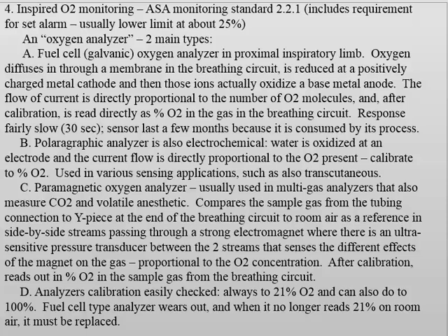There's the so-called polarographic, which is electrochemical, very rare anymore, unlikely to be the subject of a question. The paramagnetic oxygen analyzers are what's in the gas analyzers, and you know the gas analyzer has an inspired oxygen concentration on it, and there's two sources of inspired oxygen concentration on the anesthesia machine. Most people don't realize that. And the idea being that you can read there how it works with the comparison of the various sources.